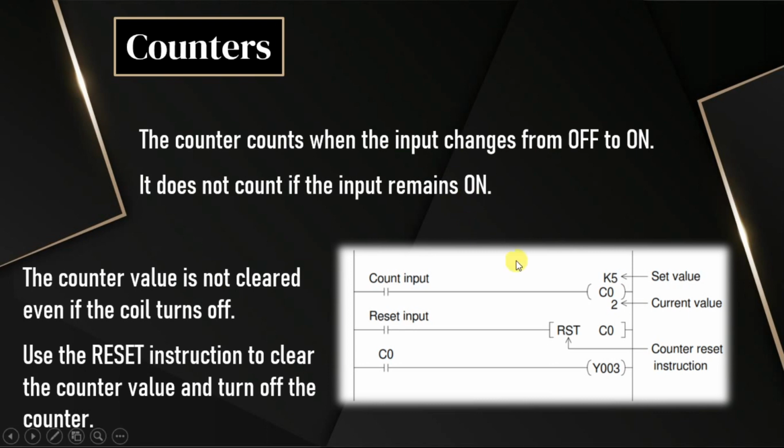This is the example program which is given here. It is almost the same as timer logic, right? If you see, one input is there and one output counter function is assigned here. Using the contact of the counter, we are turning on an output Y3. But we need one extra input, which is called a reset input, to clear the counter value.